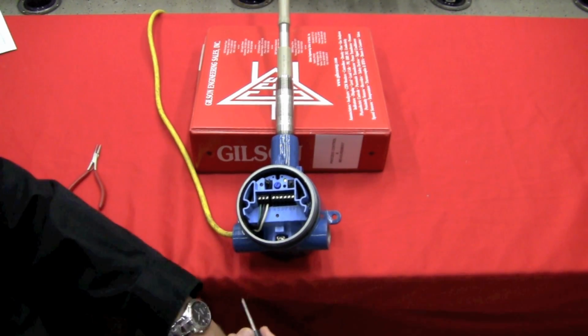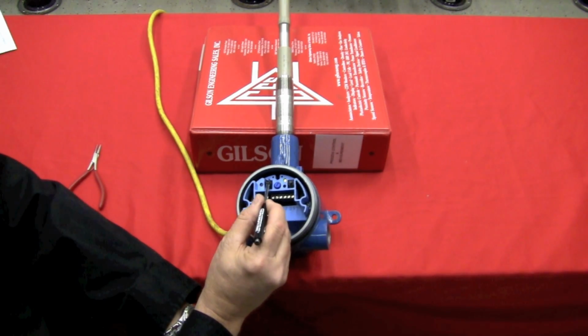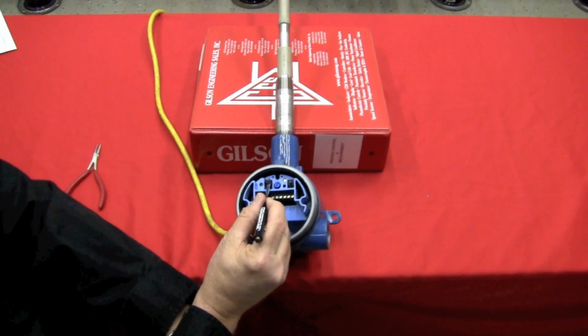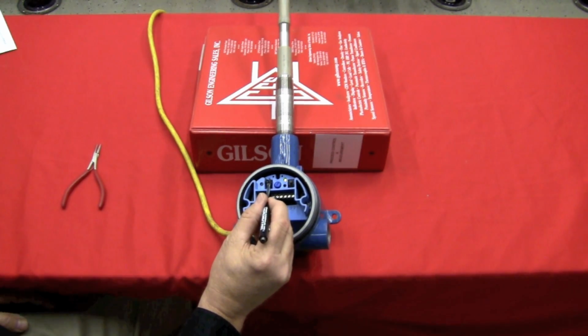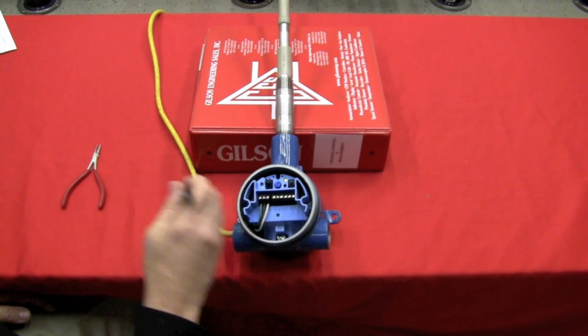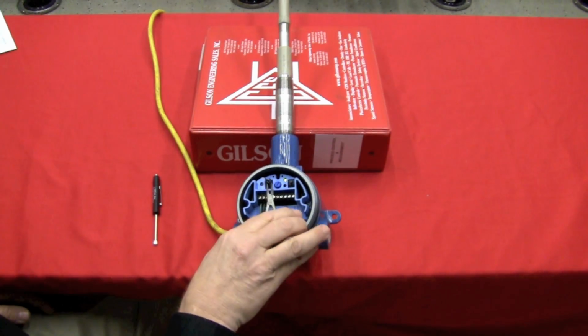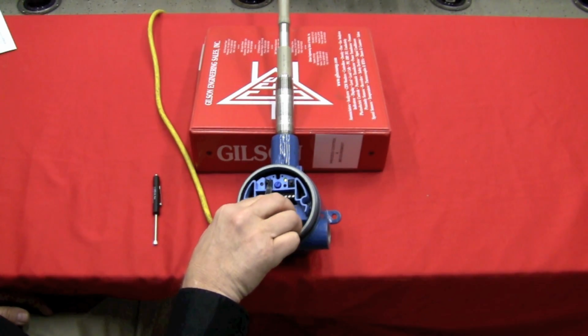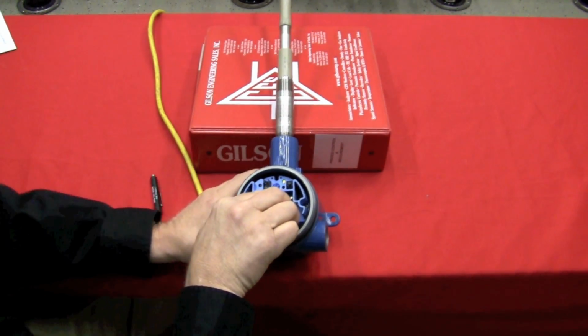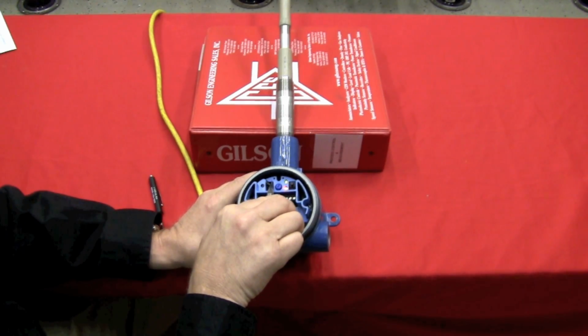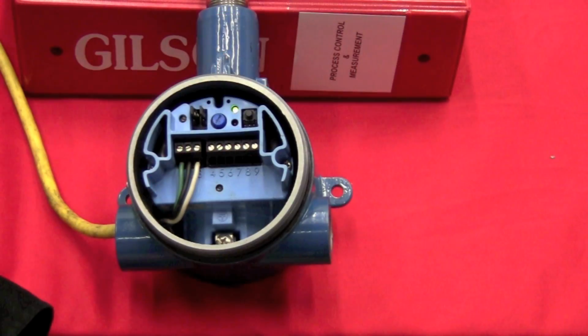Now, the next thing you'll have to set up on here is this jumper here, which is either a high-level fail-safe or low-level fail-safe jumper. In the up position, that is high-level fail-safe. But if you wanted to put it in low level, all you do is take a pair of tweezers, remove the jumper, and put it on the bottom 2 sets of pins.